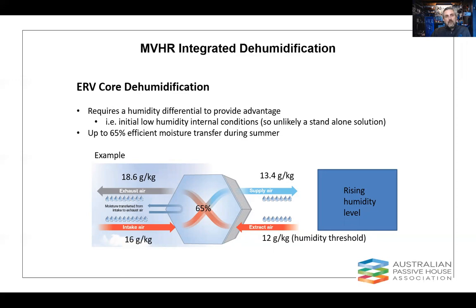When we extract that, we're bringing 16 grams potentially in, but the moisture recovery actually strips some of that away. So you can see top left hand, the exhaust air has now got more humidity in it than the intake air. But importantly, the supply air at 13.4 grams has actually been reduced from 16. So what's obvious here though is that we're going to accumulate moisture in the building still. We've been extracting 12 grams per kilo, but we're actually putting 13.4 in. So this requires some ancillary dehumidification as well. And we also needed some ability to get to 12 grams per kilogram to begin with.